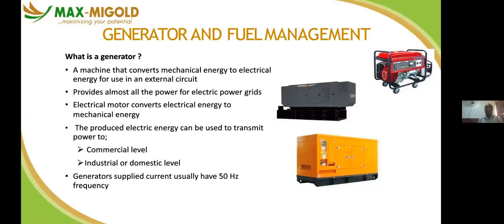The produced electric energy can be used to transmit power. Whatever you generate from your generator can be used at commercial level, industrial level, or domestic level. Generator supply currents usually have 50 hertz. The frequency must be taken into consideration. The range is between 49 and 52. Anything outside this is out of range, and some appliances will not operate if the frequency is out of range. So the well accepted one here in Nigeria is 50 hertz. Work to ensure that your generator is delivering at 50 hertz.